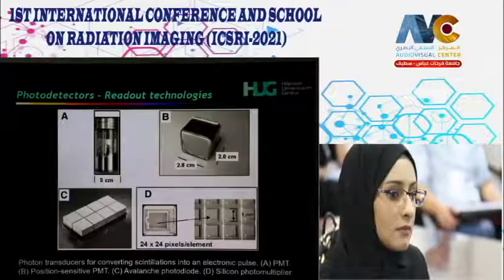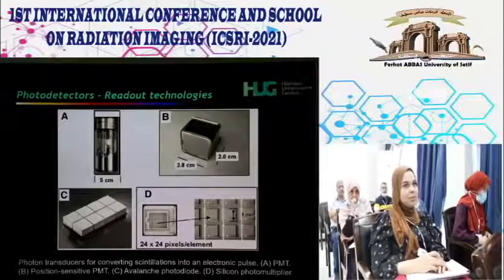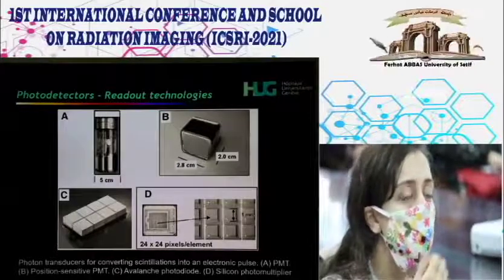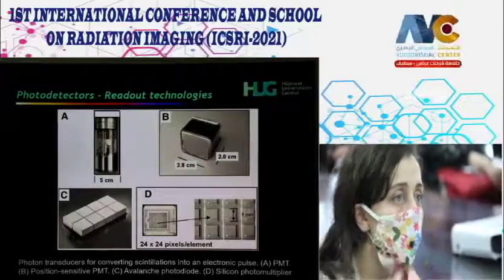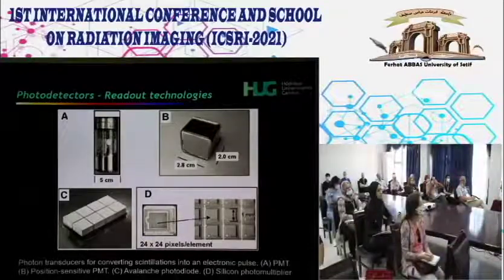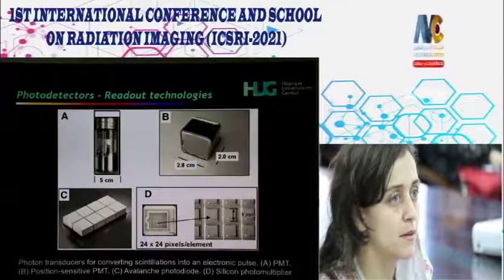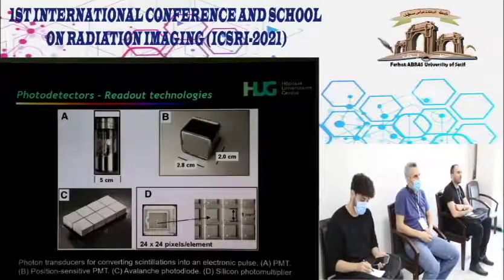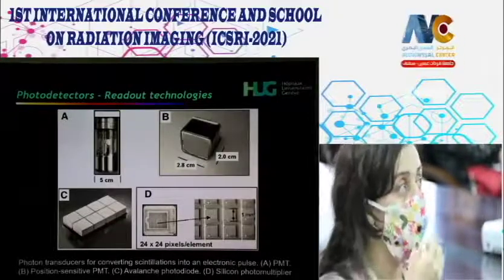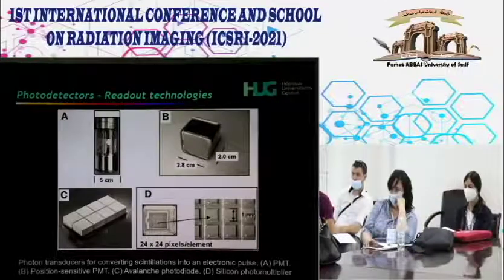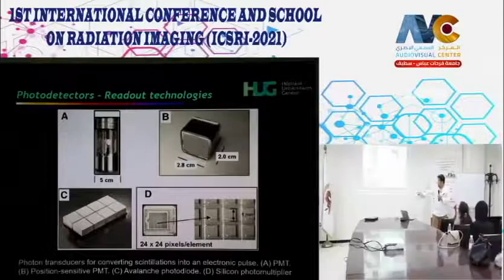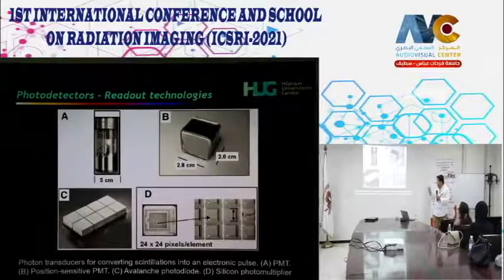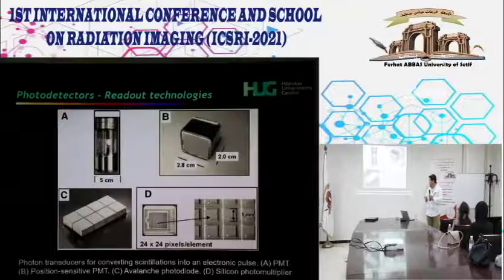Readout technologies include conventional PMTs, position-sensitive PMTs for higher resolution (small animal imaging), and MR-compatible detectors. Standard PMTs cannot operate in high magnetic fields—the field disrupts metals and the high voltage. Avalanche photodiodes (APDs) and silicon PMTs are MR-compatible, enabling their use in SPECT/MRI and PET/MRI hybrid systems.